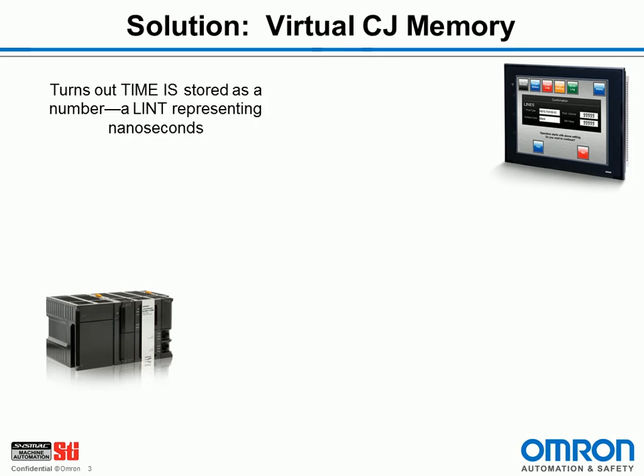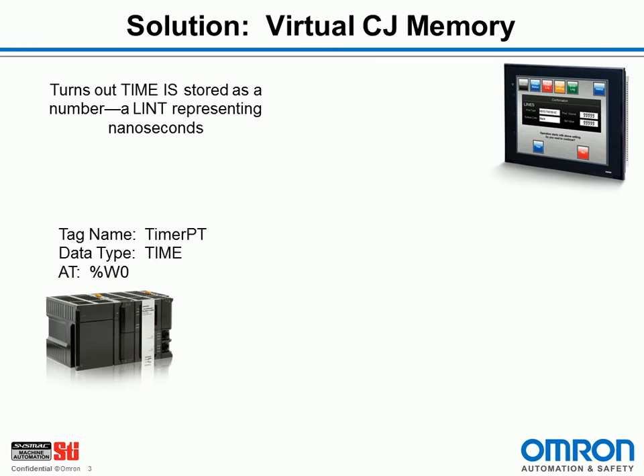So another fact you need to know is that the time data type actually is stored as a long integer. And it's a long integer representing nanoseconds. So a one with nine zeros after it would represent one second. So if I was to add an AT specification in the variable table for my timer PT variable, that would then link the data for that tag with the CJ virtual memory. So %W0 would be like work area word zero in a CJ.